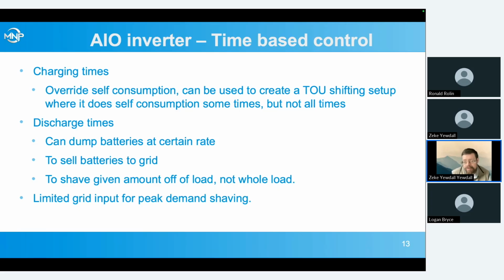You have to be careful when using this to reduce your grid input, because if you can never draw more than 4,000 watts from the grid and your average demand over the whole day is more than 4,000 watts, you better have the solar to make up that difference, or else you're going to run your batteries down and have to do an emergency switch back over to the grid. So make sure you've got enough solar if you're doing limited import from the grid, that you're not going to run into a situation where you've run out of power.